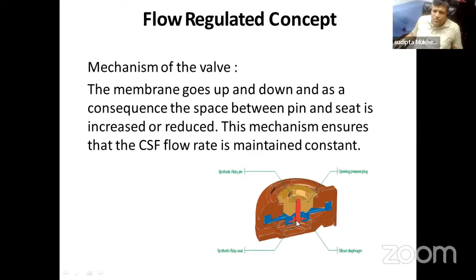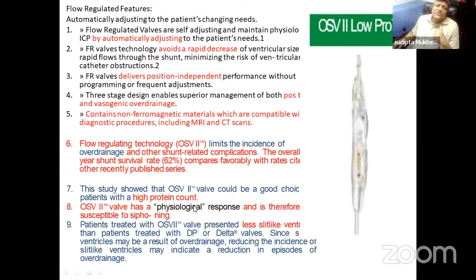Now the flow control valve has some properties. It is automatically adjusting, avoids rapid decrease of the ventricular size, and delivers position independent flow. That means a person can be supine or standing, and the same flow will continue. There is less chance of over drainage, and it contains non-ferromagnetic material, so it is not hampered by MRI. It can be used even with a high protein count, it can maintain the physiological response, and there is less chance of slit ventricle. So the flow control valve has nine advantages over the differential pressure valve.